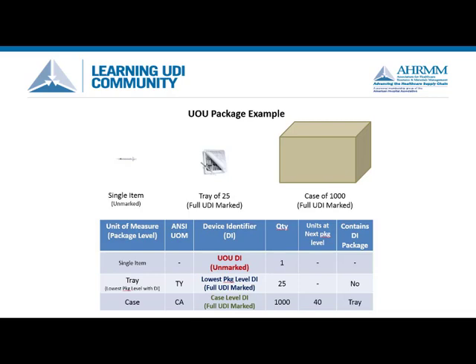There are printed barcodes at both the full case level and the tray level, but there are no barcodes available on any of the individual syringes. In this case, the FDA requires the manufacturer to assign an additional device identifier, or DI, to the individual syringe. This identifier is also known as the unit of use level. The UOU DI is not marked on the product.